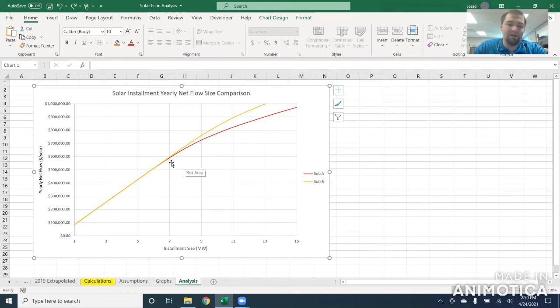Below, we looked at an undersized installation of 3, a right-sized one for this area's load at 5, and an oversized one at 7. You can see how much money we lose with an oversized installation due to the curtailment that would happen. Looking at that 5 megawatt size, we barely lose any, so that looks to be about the right set point. Thank you.